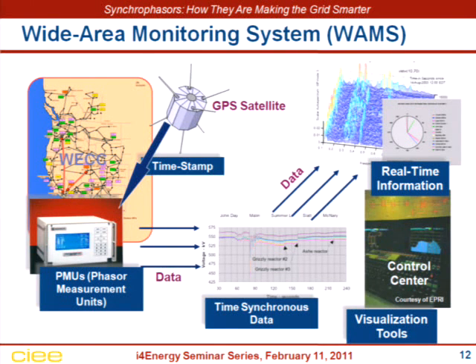The PMUs basically sample the analog signal once a cycle, so that's 60 times a second. So everything you're measuring has 60 measurements a second on that variable, accurately time-stamped so you can correlate it with any other measurement around the system in virtual real time. I say virtual real time because you're going to have some latency in the telemetry transmission, the computation, and so on, but you're still talking milliseconds, not months, to do a correlation kind of study.